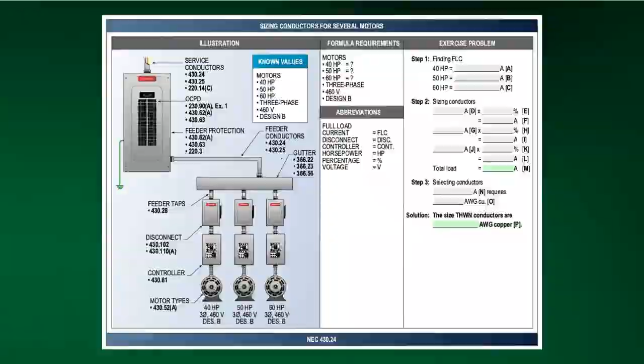Let's look at some text here. I want to point something out: they added a new definition in the 2023 NEC for a motor branch circuit. It says the circuit conductors, including equipment, between the motor branch circuit short circuit and ground fault protection device for an individual motor. Do you see that? That alone, just that definition, destroys exactly where he's saying that it's a feeder.